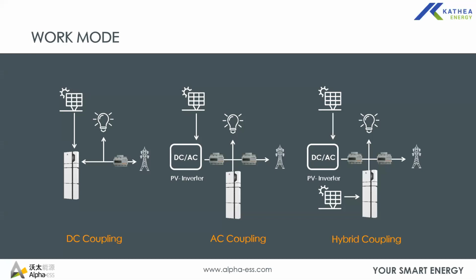So you can actually maximize your PV. You have a grid tie inverter to supply the bulk of the loads, and then when you have load shedding, the Alpha system will be there to give power to your backup loads. That is the loads that are essential during load shedding. So please note that this PV inverter is not installed at the output of the Alpha. It's installed on the grid line, like at the input of the Alpha on the grid line.